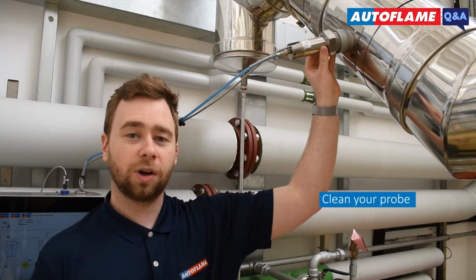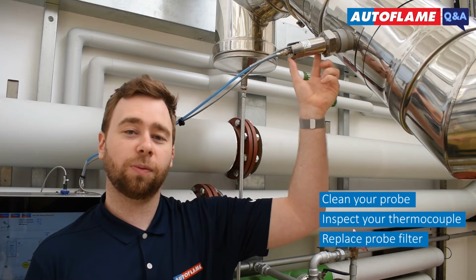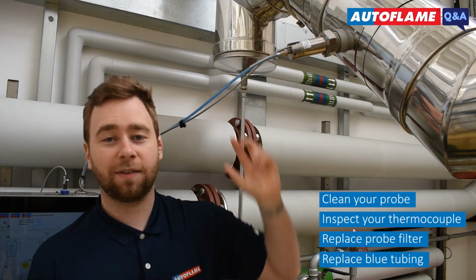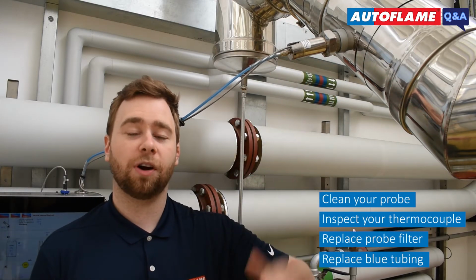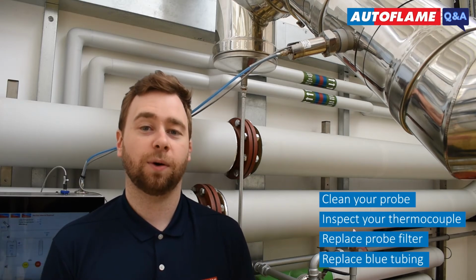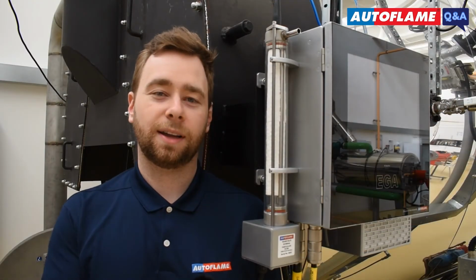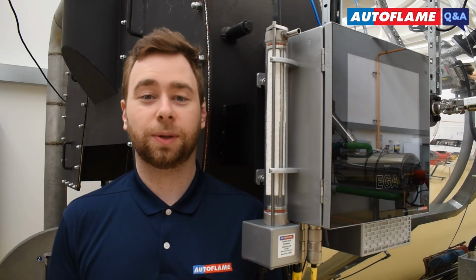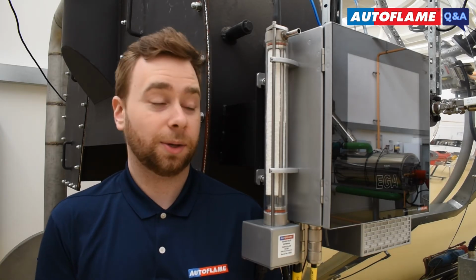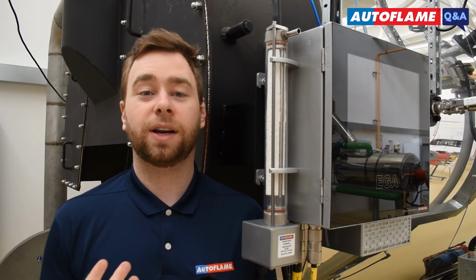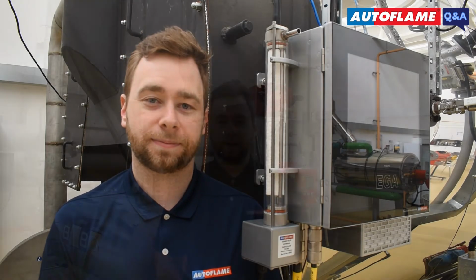Your EGA sampling probe can also be removed from the stack and shipped back to us for service, preferably in its original packaging too. You may need to cap the hole in the stack. Once received, we will clean your probe, inspect your thermocouple, replace your probe filter and your blue tubing. However, we can supply the blue tubing and the probe filter to your local technology centre for on-site replacement. If you are sending your external particulate filter back to us, we also recommend using the original packaging. You can see these devices feature a glass cylinder which, if struck, can smash in transit.